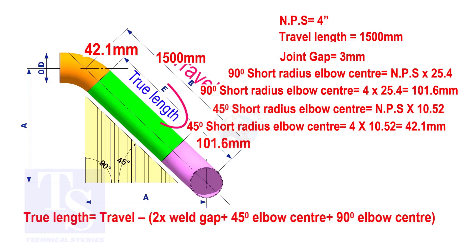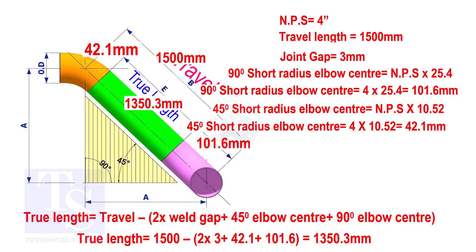To calculate the true length of the pipe, subtract two weld gaps plus both elbow centers from the travel length. The true length of the pipe is 1350.3mm.